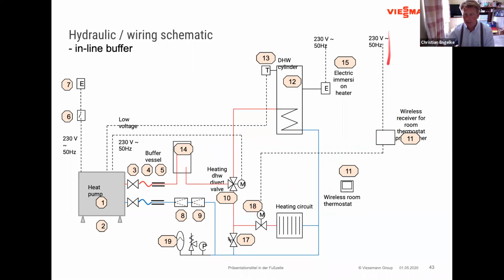Electrically, same here as well. We have a wireless room thermostat, which then controls the two-port valves in the building, the zone valves, and then we only electrically wire the three-port valve to the heat pump and a sensor for the hot water also directly to the heat pump. And that's all that is needed. So this is more like a typical installation you will see with any gas boiler or oil boiler installation right now.